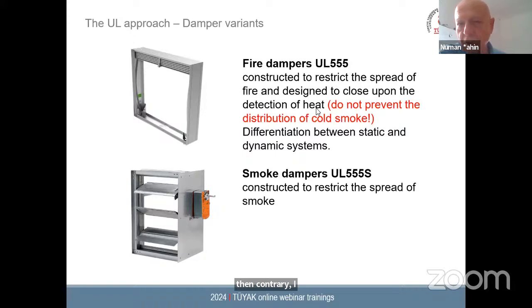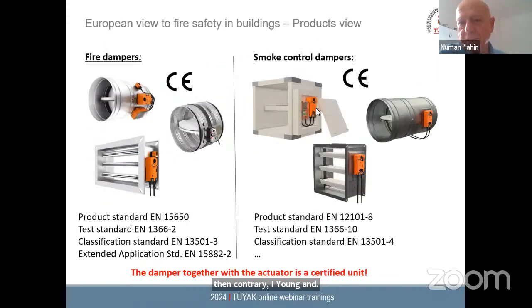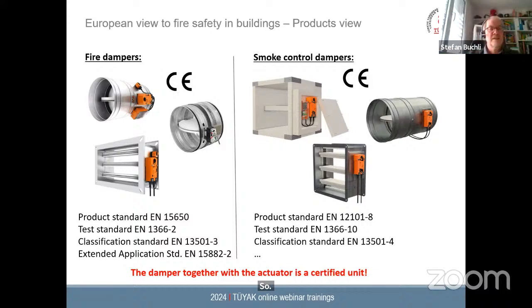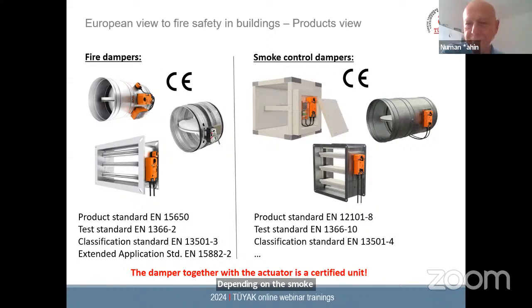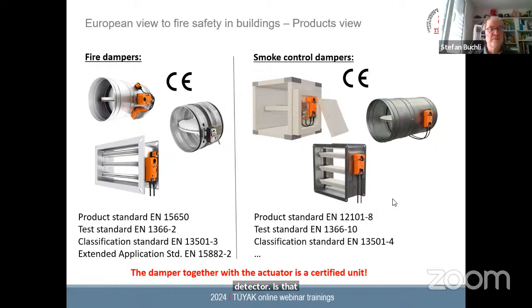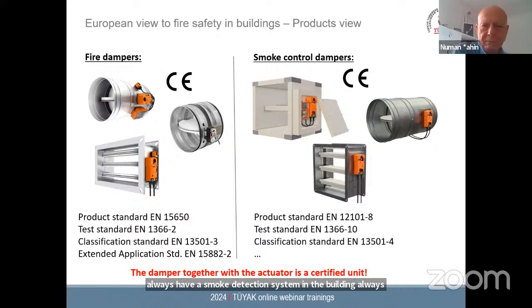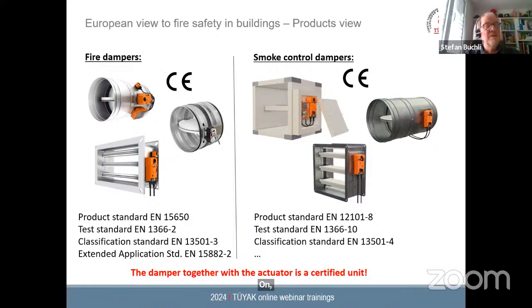They work as a fire damper, but not a smoke damper. So the question is, if there are no smoke sensors, no detection sensors, is there any solution for that? But all the smoke dampers are working according to the fire alarm panel, depending on the smoke detector. Is that correct? Yeah. So when we talk about a smoke control solution, which is a separate system, you always have a smoke detection system in the building, always. Okay. Sorry. On the fire damper side, you see everything, of course.